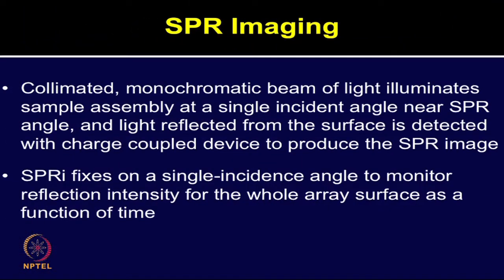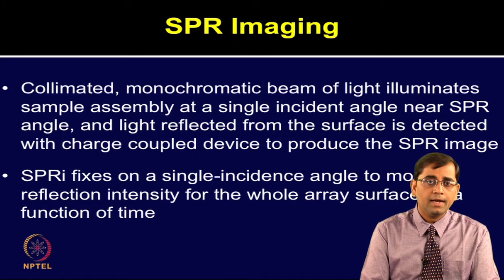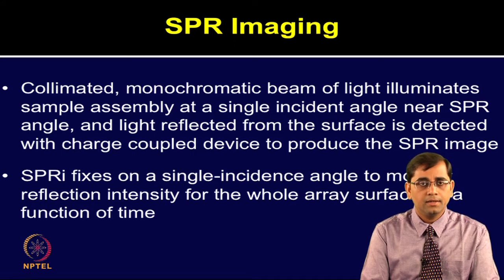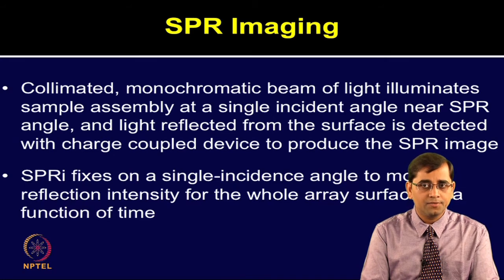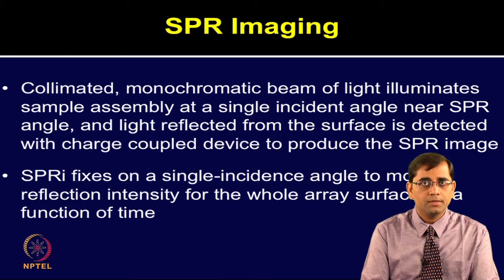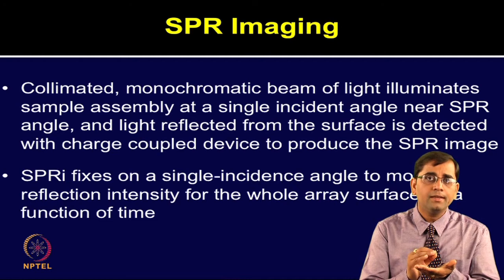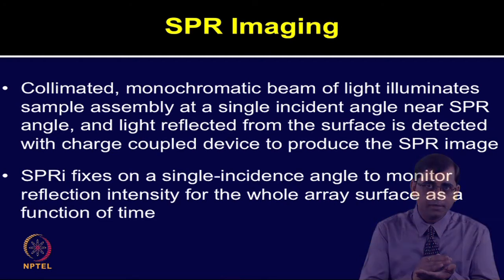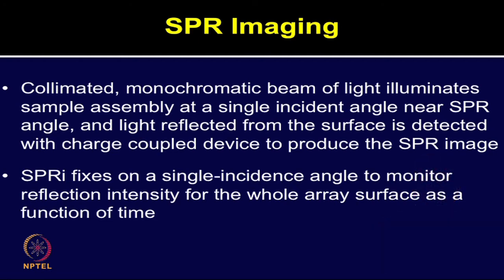The SPRi technique involves a collimated monochromatic beam of light which illuminates the sample assembly at a single incident angle near the SPR angle, and light reflected from the surface is detected with a charge-coupled device to produce the SPR image. SPRi fixes on a single incident angle to monitor the reflection intensity for the whole array surface as a function of time.